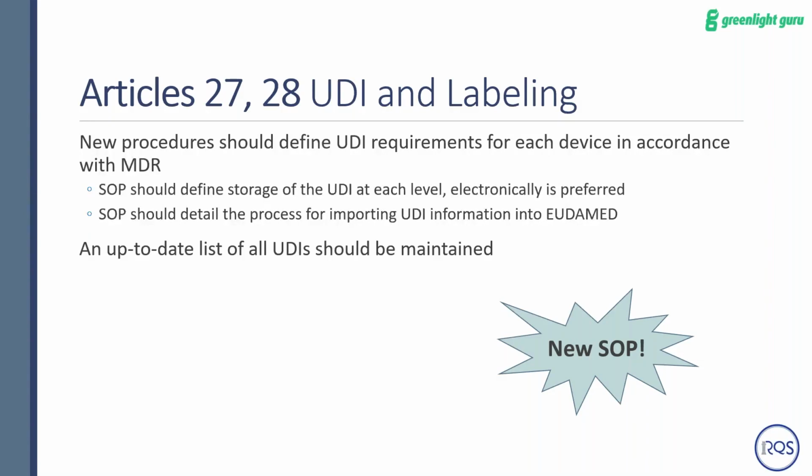And then part of the requirements for MDR is that you have to define storage of UDI in each level. Electronically is preferred, and that's straight from the standard. So you want to have an electronic method of tracking what UDIs you've issued, as well as updates to UDIs and where those devices are. And then your SOP, so this is a new SOP.